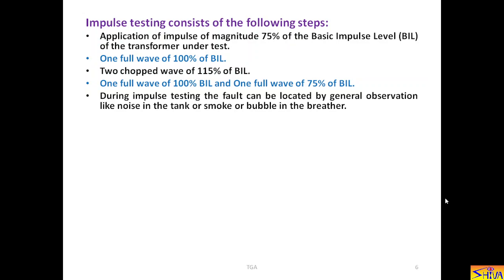During impulse testing, the fault can be located by general observation like noise in the tank or smoke or bubble in the breather. If such type of observations are there, it means the transformer has failed to withstand the applied impulses. If there is a fault, it appears on the oscilloscope as a partial or complete collapse of the applied voltage. Obviously, the voltage will collapse.